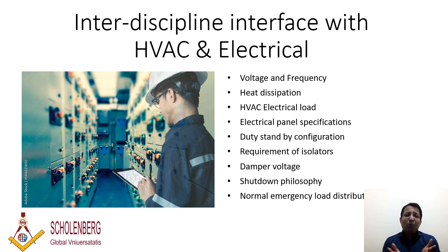Or if you don't want to do it yourself, simply approach an AHU vendor if you have contacts - give them the data and they'll tell you the motor size needed. That's a simplified and authentic source. But at the initial phase of the project, no vendor will entertain you unless you're a big client. So you need to do the calculations yourself and always give slightly oversized values to electrical so it can be optimized afterward.